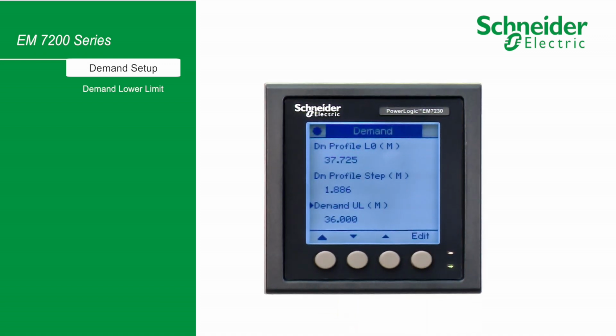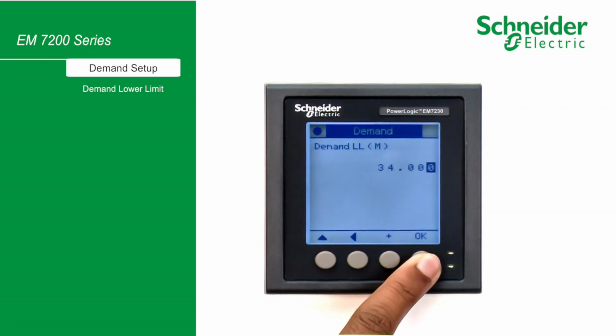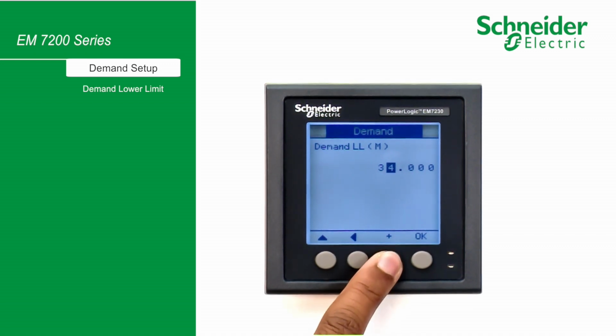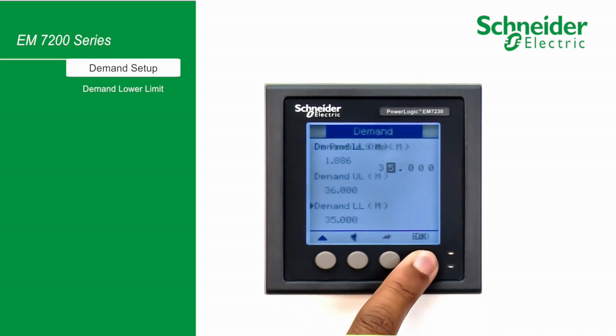Once you are done with the setting for the upper limit, the next step is to set the lower limit values. The significance of this feature is to reconnect the load whenever the demand falls back below the lower limit range, and this could happen within the demand cycle itself. You can choose 10 to 99% of the upper limit as lower limit values. Let's select 35 MW as the lower limit in this case.